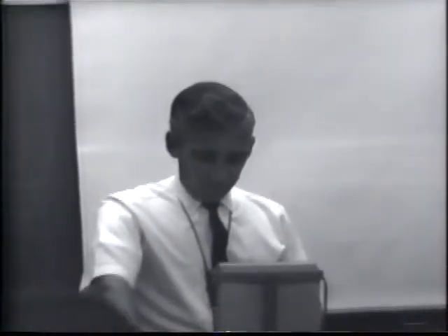We have a forced air opening, which is installed at one end of the vault, which in some cases we've used to install a shaft from this opening down to within a couple feet of the floor, and I've installed a fan there, and that's used for the cooling of the transformers.